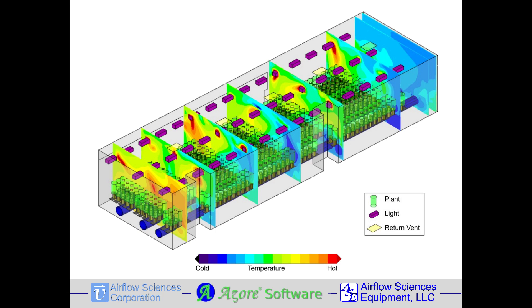Results from the initial ventilation system design indicated that one end of the room would be warmer than the other. The ability to virtually change any parameter — from flow rate to duct location to plant layout — individually or in combination, provides an efficient means of optimizing the airflow throughout the entire facility.